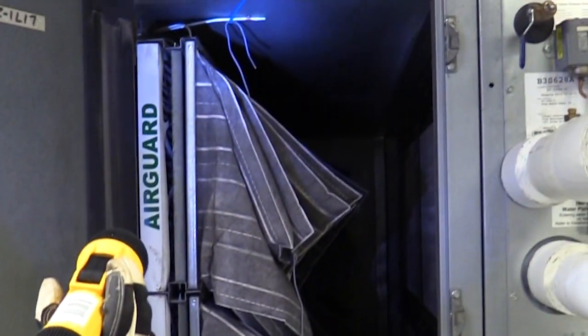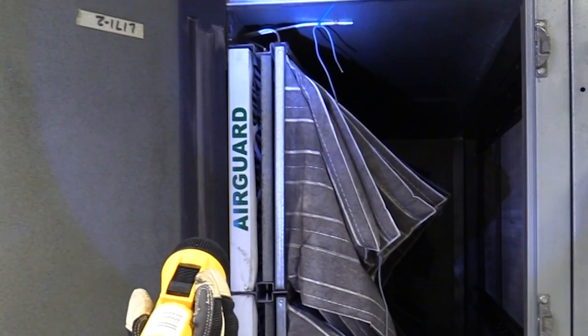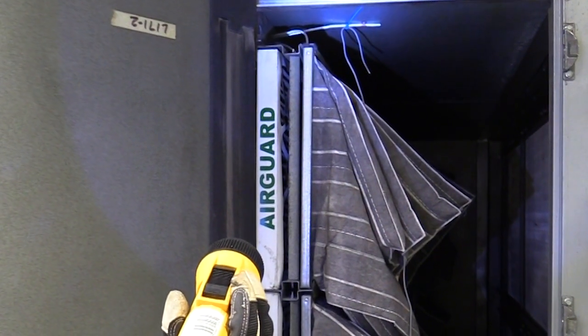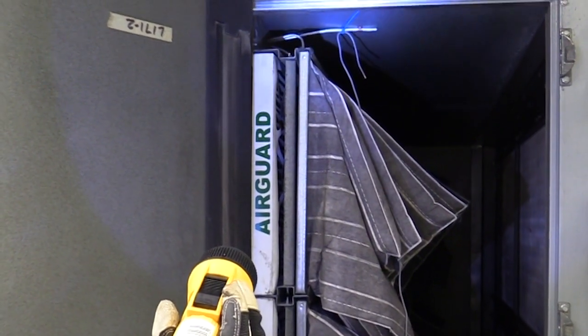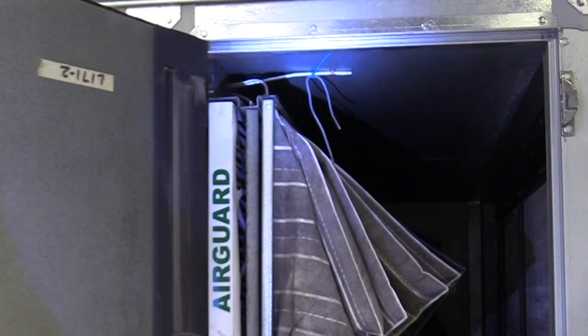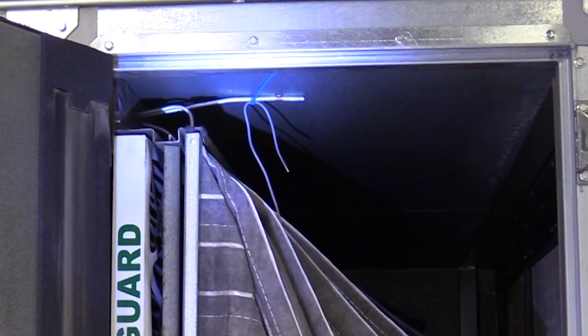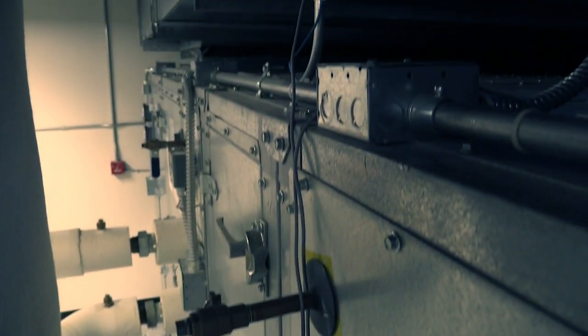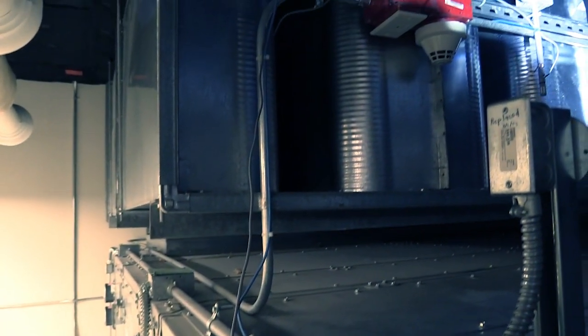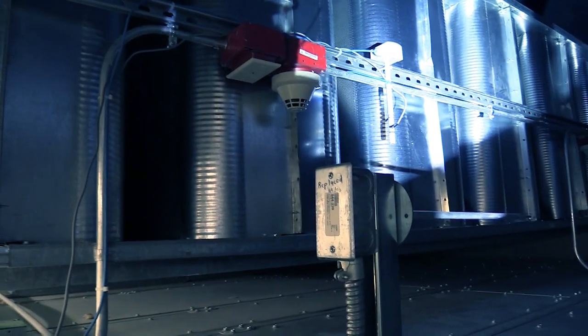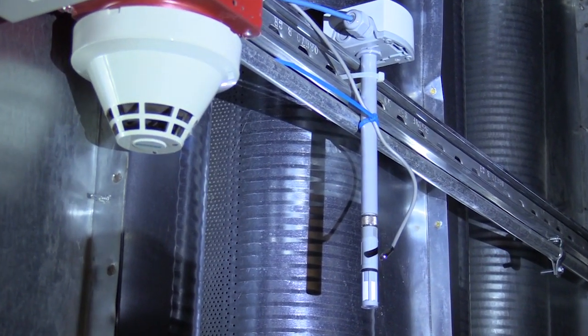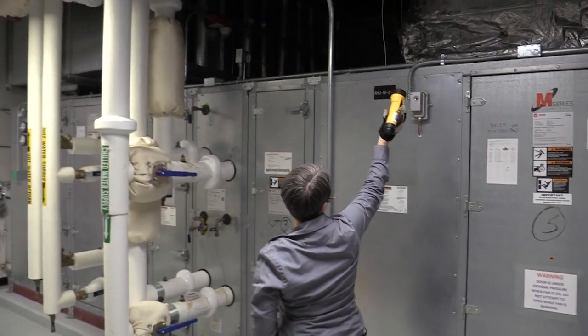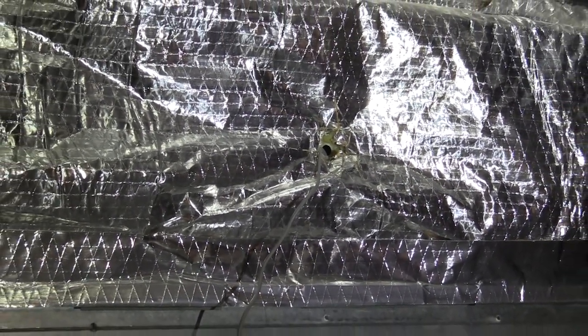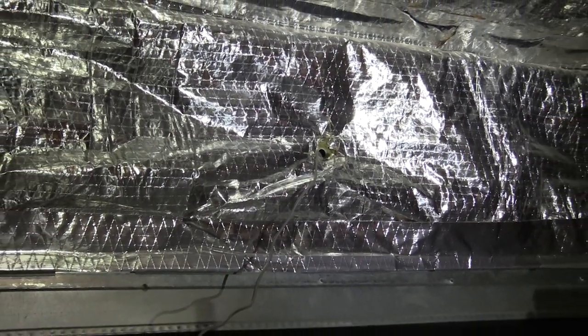And now, as you can see, I've placed another sensor in a similar way, secured in a place where it's not going to touch another surface. And this is in the mixed air chamber just past the filters. So here I've placed another sensor just in front of an outlet for the return air duct. And up here I have the supply air sensor running through a test port directly into the supply duct.